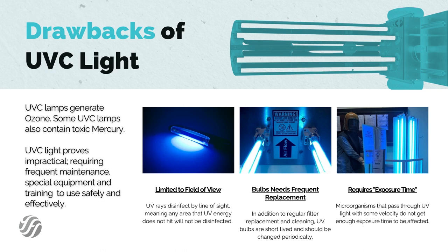UVC lamps lose their efficacy by 15% every 6 months to a year, so frequent replacement is required. Another drawback is that the system requires what we call exposure time, which could be several minutes. The system only treats areas where the UVC light shines directly, so shadow areas are not treated.